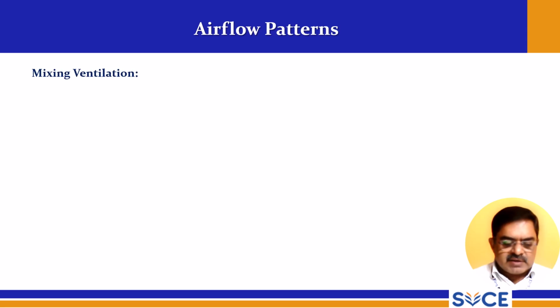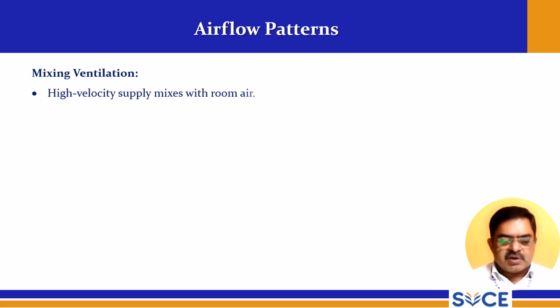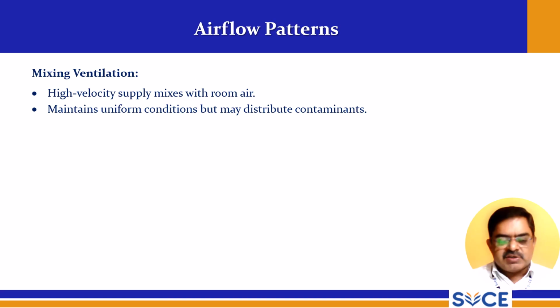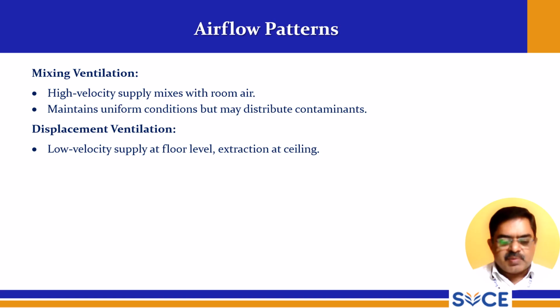So, airflow patterns. There are different types. Mixing ventilation: high velocity supply mixes with room air, maintains uniform conditions but may distribute contaminants. Displacement ventilation: low velocity supply at floor level, extraction at ceiling. So better stratification, used in clean environments.